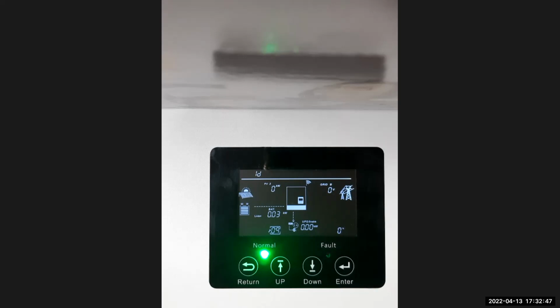The manufacturer said it can go up to 2C without damaging the battery. So that 3.6 kilowatt battery can actually give you 7.2 kilowatts worth of power that you can pull at any given time out of it. That's roughly 110 amps around there. That's more, 120, 130 amps. So this is just your discharge current amount that you can set on this inverter.